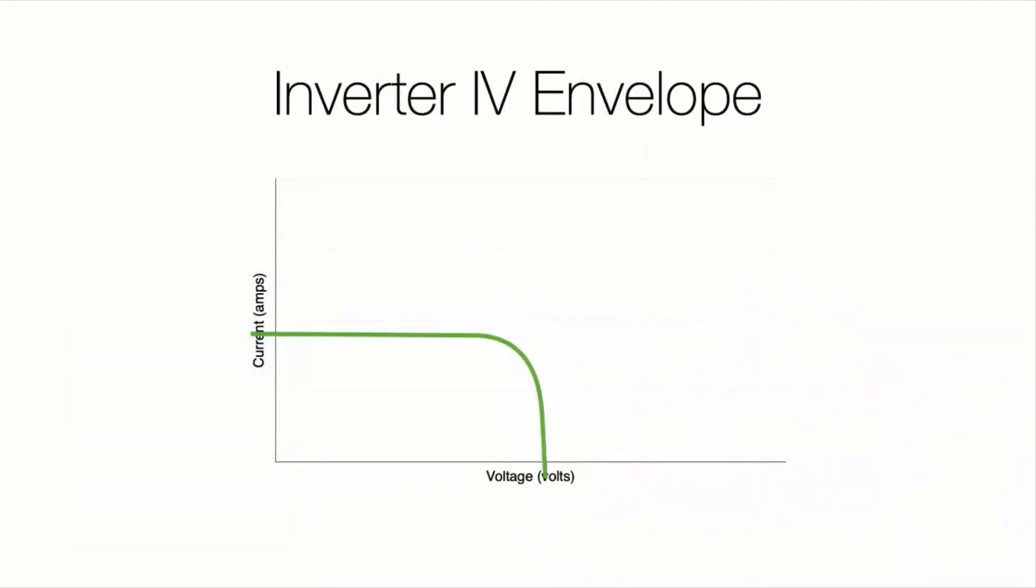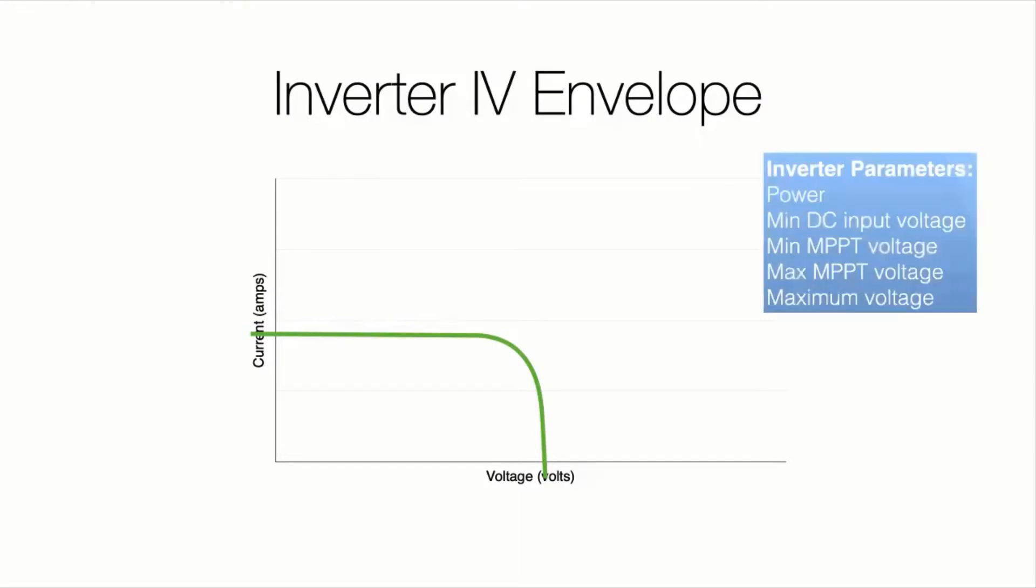And one interesting point here, I can create an inverter IV curve, really call it an IV envelope. I can do that based on the parameters of a typical inverter. I can have a minimum voltage operating for the inverter and a maximum voltage. This gives me my operational window that the inverter is designed to work in. And it will have a minimum max power tracking point and a maximum max power tracking point.